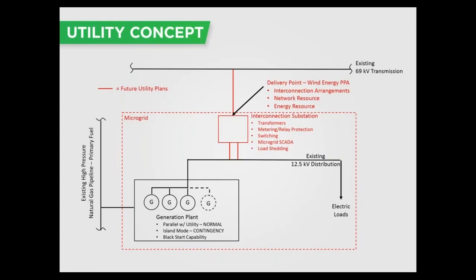The generation plant that you see in the bottom is going to start out as a 4 meg natural gas reciprocating generation plant. We have a large natural gas pipeline very near to the physical location. That was one of the criteria we had for locating the generating plant where it is: the physical location close to the fuel source, obviously, and then, of course, close to the load. So it will be adjacent to our distribution. In that, you see there's existing 69 kV transmission lines that feed the transformer, and the delivery point up there is where you see that would be our point of common coupling.